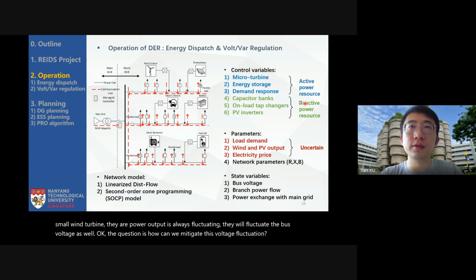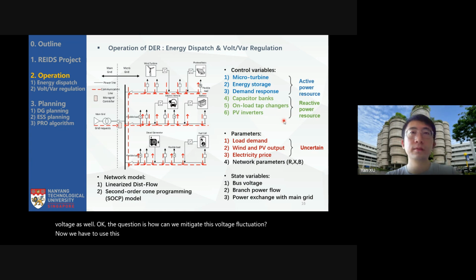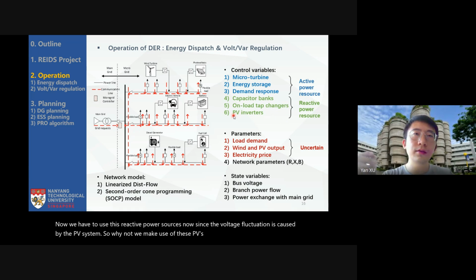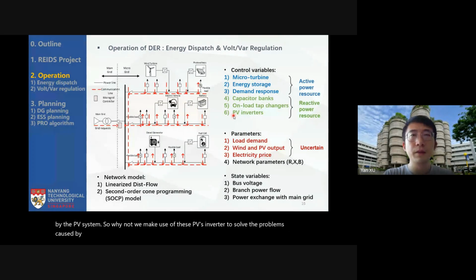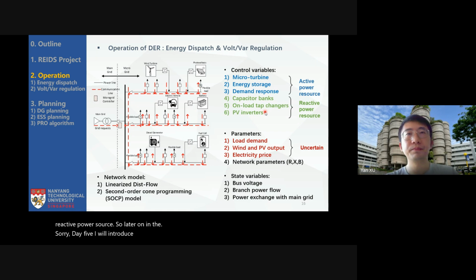Now we have to use these reactive power sources. Since the voltage fluctuation is caused by the PV system, why not make use of the PV's inverter to solve the problems caused by themselves? So this is the major idea or motivation for using PV inverters as a reactive power source. Later on, in day 5, I will introduce more details on that.